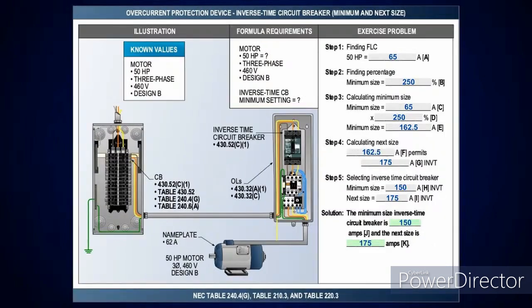So when I look at this next, and it's an inverse time circuit breaker, and I look at the table for my 50 horsepower, 460 volt three-phase design B, it's going to tell you take it at 250%. So if you notice, based on the table, for non-time delay, we took it at 300%, time delay 175. Then when I got up to my instantaneous, I took it at 1100%. Then I had to look at C3, which allowed me to go to 1700%.